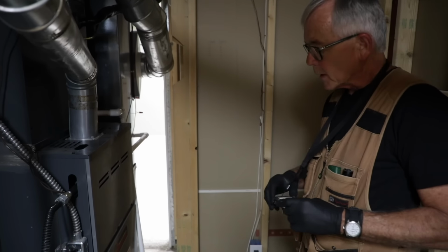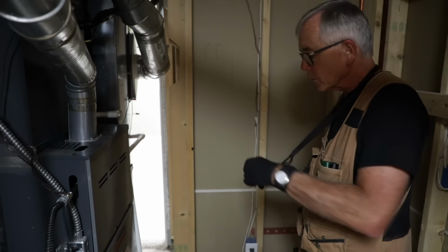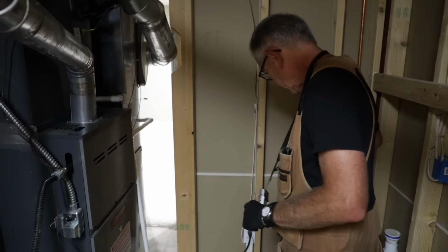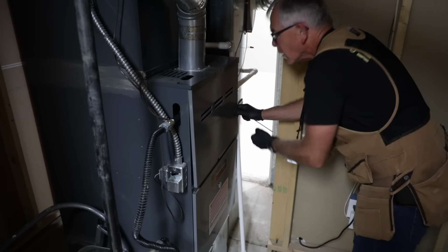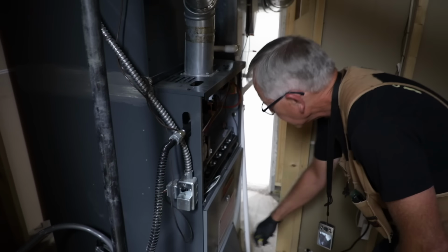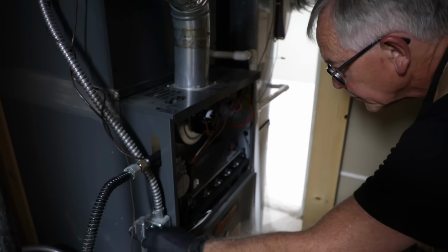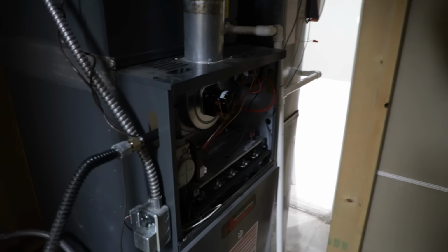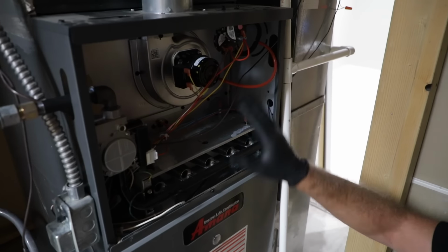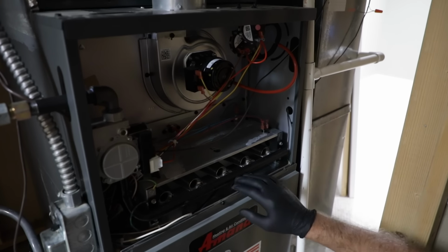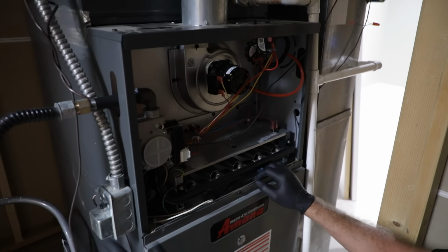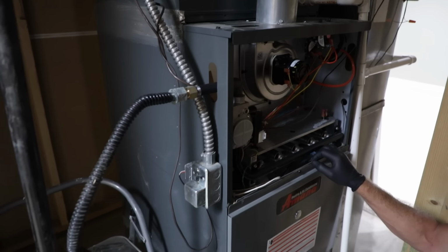We're down here at the furnace in the basement, and basically this is just a mechanical room for this type of equipment. I'm going to go ahead and take a reference photo of the furnace, and I am going to remove the front cover so I can view everything on the inside. Okay. We'll see if we can get this furnace to ignite. I'm going to take a few reference photos. When I first look at the furnace, I've already discovered that this is a gas forced air type furnace. It's an upflow, and over here I can see that I've got a fuel line, and this is a natural gas fuel line.